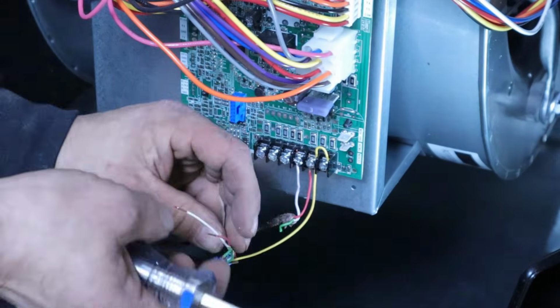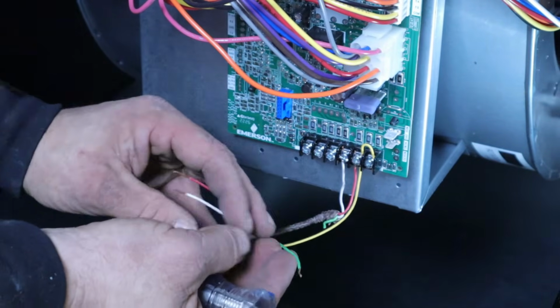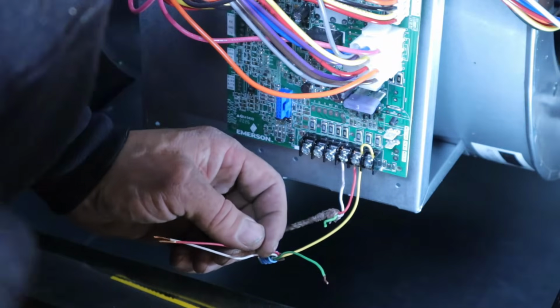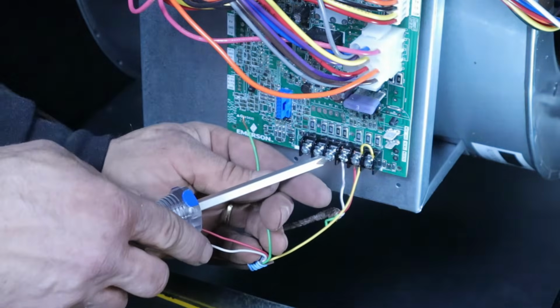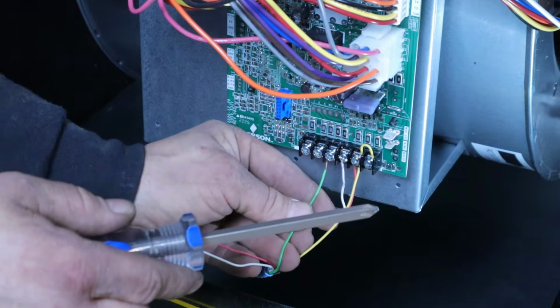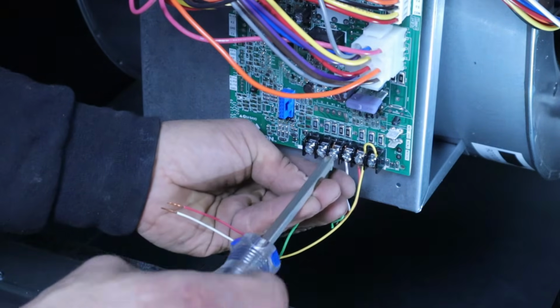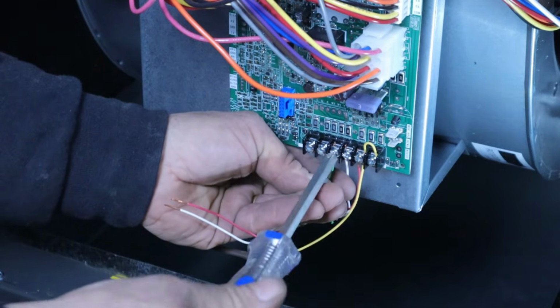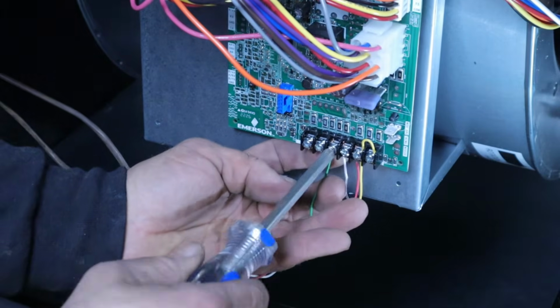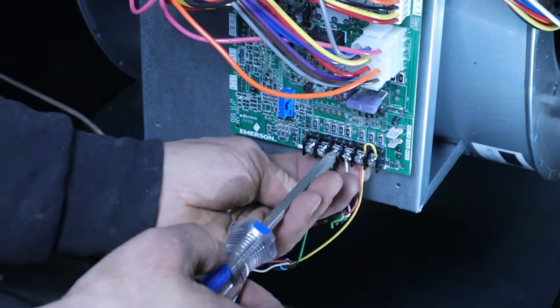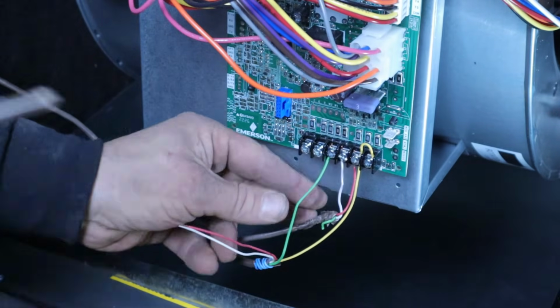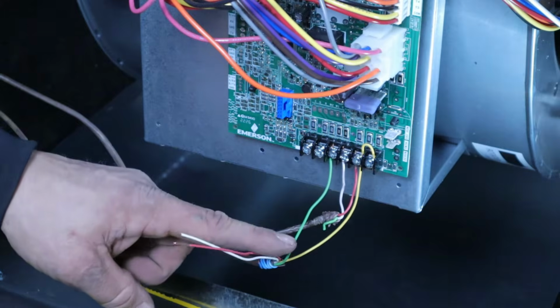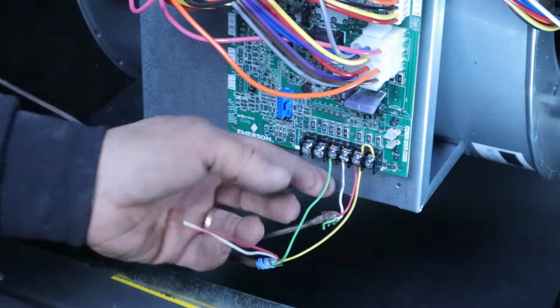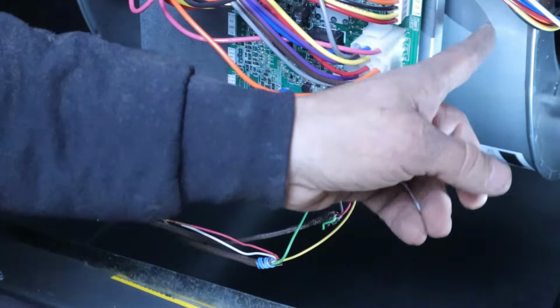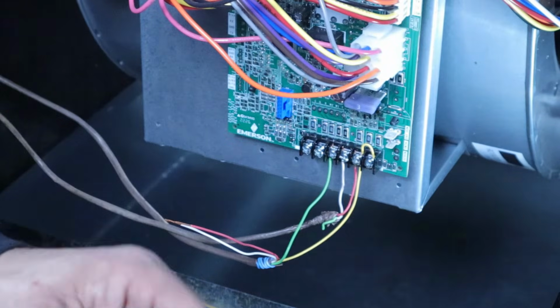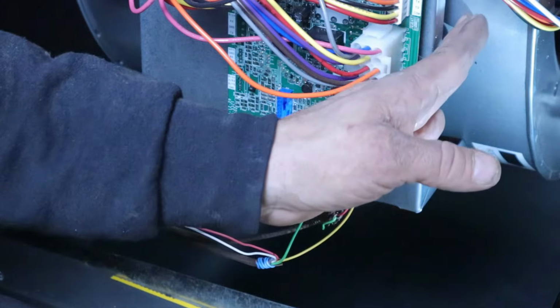So now we have our red, white, and green off of our thermostat. Our next terminal here is the G terminal, and I'm going to hook up the green wire to that. There's a function on your thermostat for the fan that allows you to set it to auto or on. When you turn that switch on your thermostat to on for the fan, it sends power down this green wire, and all this does is run the blower motor right here and circulate the air through your home. So it's not activating heating or cooling, it's just running the blower itself.